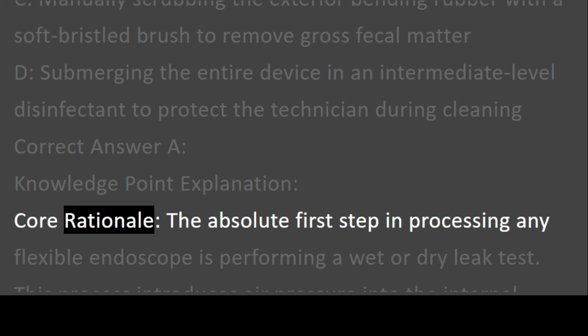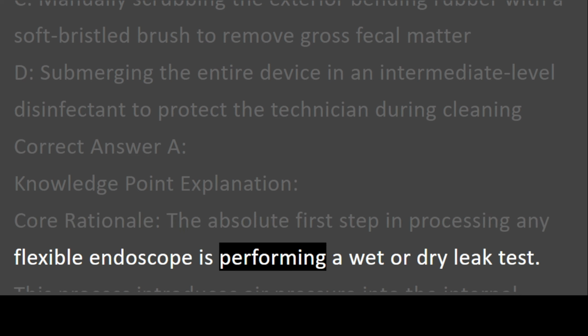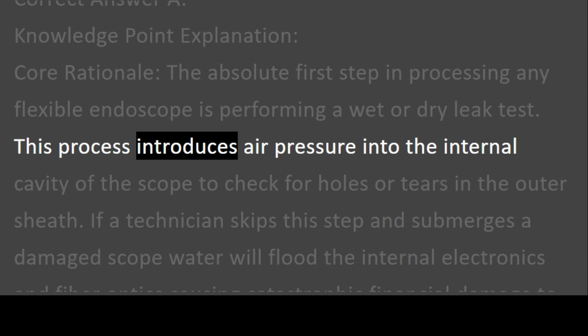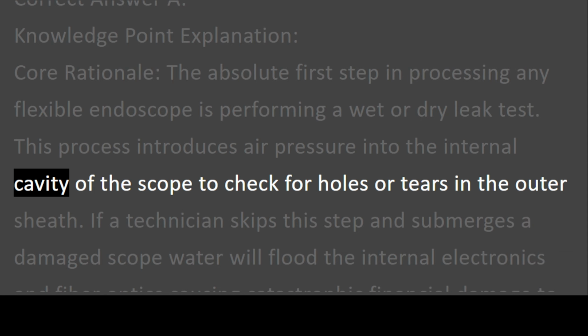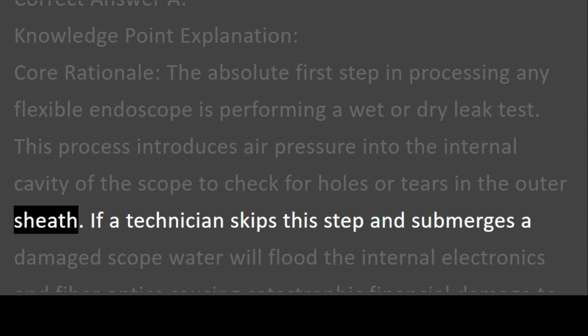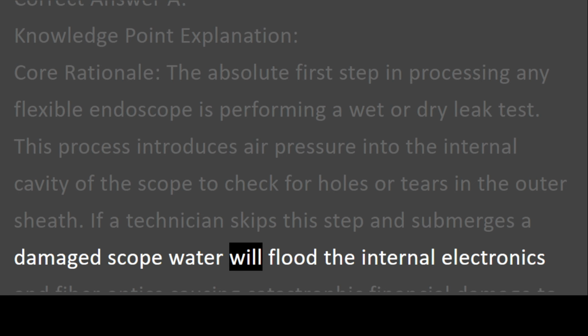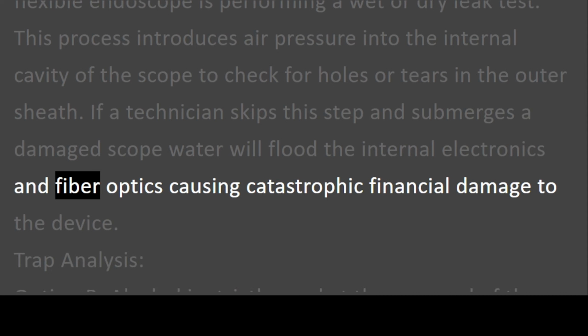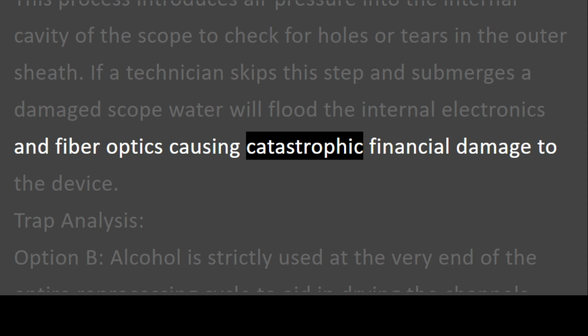Core rationale. The absolute first step in processing any flexible endoscope is performing a wet or dry leak test. This process introduces air pressure into the internal cavity of the scope to check for holes or tears in the outer sheath. If a technician skips this step and submerges a damaged scope, water will flood the internal electronics and fiber optics, causing catastrophic financial damage to the device.